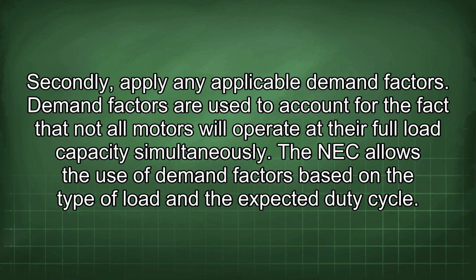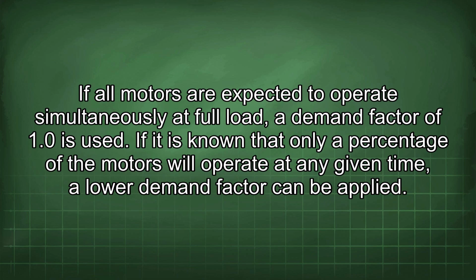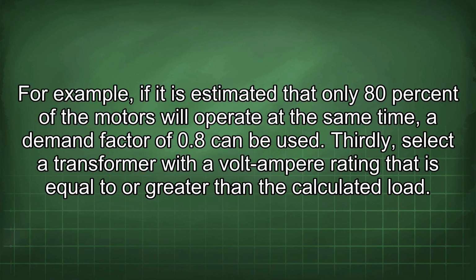Secondly, apply any applicable demand factors. Demand factors are used to account for the fact that not all motors will operate at their full load capacity simultaneously. The NEC allows the use of demand factors based on the type of load and the expected duty cycle. If all motors are expected to operate simultaneously at full load, a demand factor of 1.0 is used. If it is known that only a percentage of the motors will operate at any given time, a lower demand factor can be applied. For example, if it is estimated that only 80% of the motors will operate at the same time, a demand factor of 0.8 can be used.